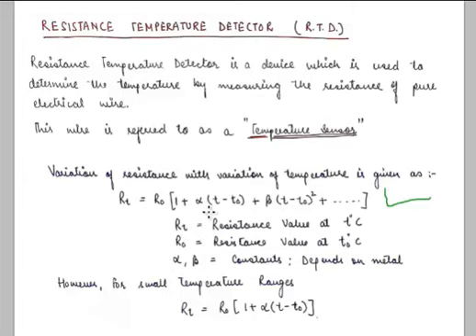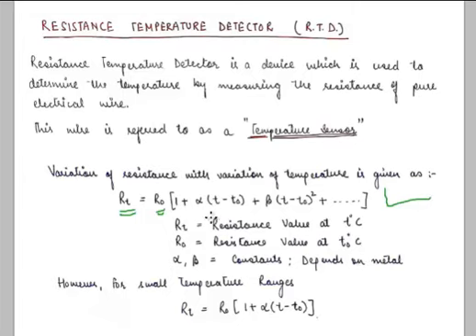The governing equation is: RT = R₀ × (1 + α(T − T₀) + β(T − T₀)² + ...) extending to higher orders of (T − T₀). Here, RT is the resistance at temperature T degrees Celsius, R₀ is the resistance at reference temperature T₀, and the constants α, β and subsequent terms are the temperature coefficients of resistance. The value of these constants depends on the type of metal used for the RTD.